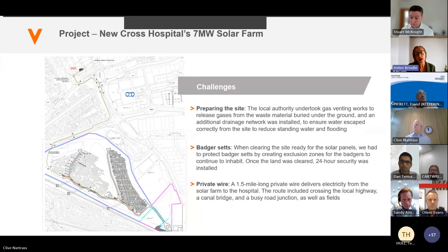Obviously, building on a landfill site had significant issues. So this is partly with the local authority and the Environment Agency, making sure that there was a gas monitoring and ventilation system in place.